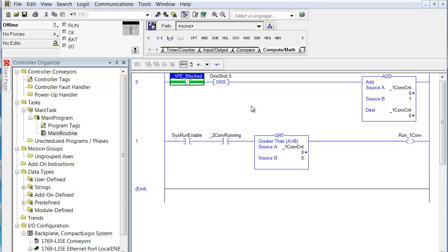Now, in the manual, when you got to this point, it had a little description of this rung, and on this instruction it said on the trailing edge of a carton leaving 2 PE, one shot the add instruction. This increments the count each event of a carton clearing 2 PE onto 2 conveyor. You probably have seen the error we mentioned, actually clearing 2 PE onto 1 conveyor. So it's not an error as far as code writing goes, it's a less than optimum logic.